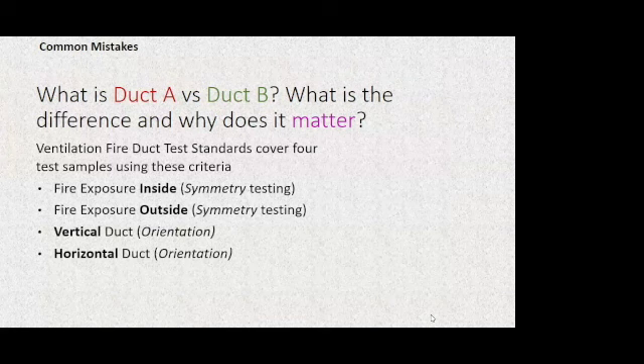So you need to know that duct A and duct B are very, very different. You need to know that they don't always test duct B, that they can get listing cards. You just saw one where the only thing they tested was duct A, and they will use it for all purposes under the sun if you let them. And we are not just splitting hairs esoterically. I'm going to show you the pictures of what happens when we use the wrong ductwork and we have real fire exposures. We're going to talk through the real world fire scenarios where those same problems that we see in those photographs are going to happen if we don't fix it before it gets approved.